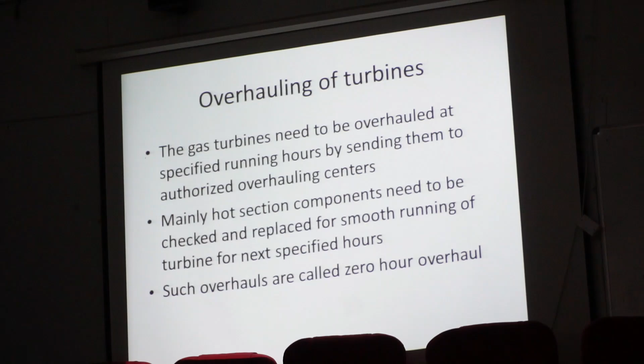Overhauling of gas turbine. Since our blades are highly subjected to continuous exposure to 700-800 degrees centigrade temperature, these turbines are meant for only 25 to 30,000 hours of continuous running. After that, we will have to remove this, send it to the OEM manufacturer or overhauling center of the turbine, and there they will completely open the turbine, see what components are to be replaced. They will replace them and send it back to our place.